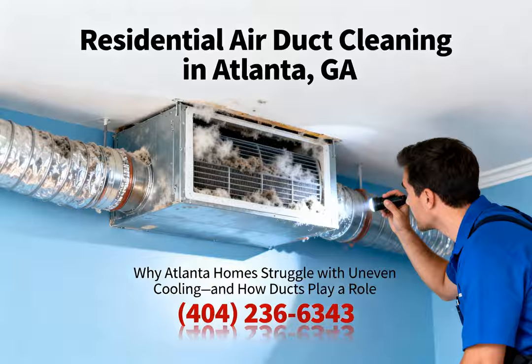They cannot reproduce, which means they cannot form what technicians call bioslime. Bioslime, another lovely visual. I know, right? Bioslime is a sticky biological matrix that loves to grow over wet AC coils. And from an engineering standpoint, bioslime is a massive problem because it acts as an insulator. Oh, so it blocks the cooling. Exactly. If your freezing cold coils are wrapped in a blanket of slime, they cannot properly absorb the heat from the air blowing over them. It blocks the heat transfer process.